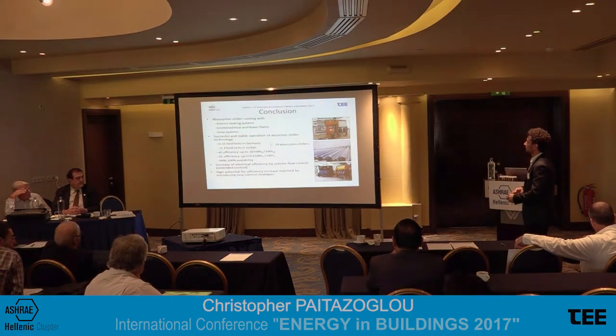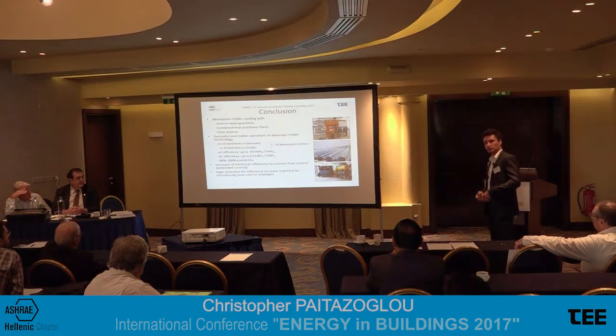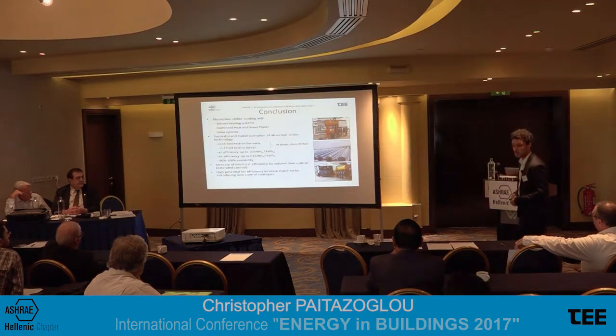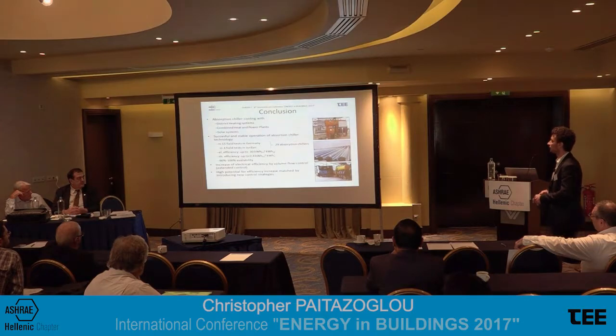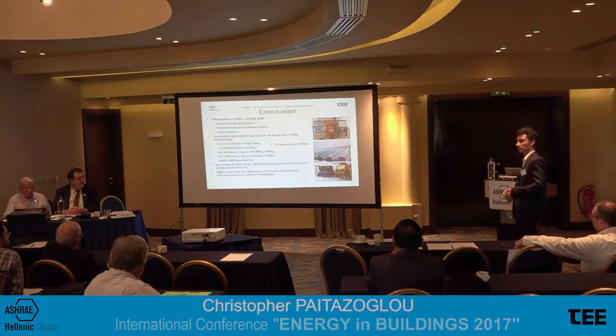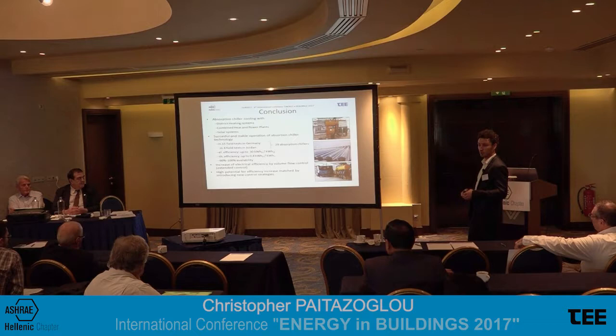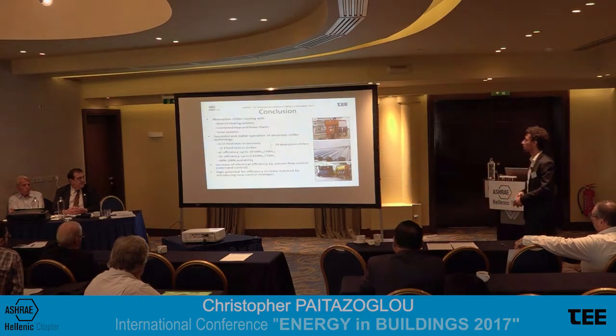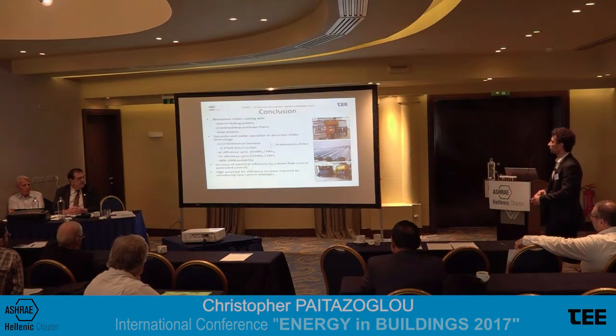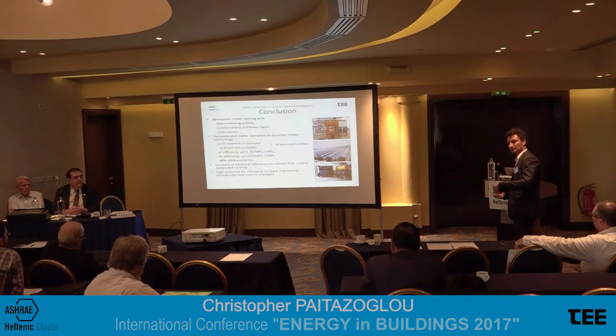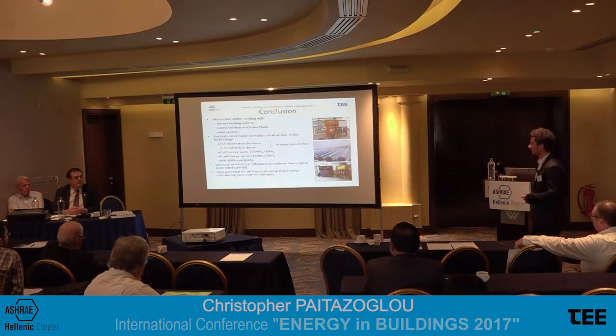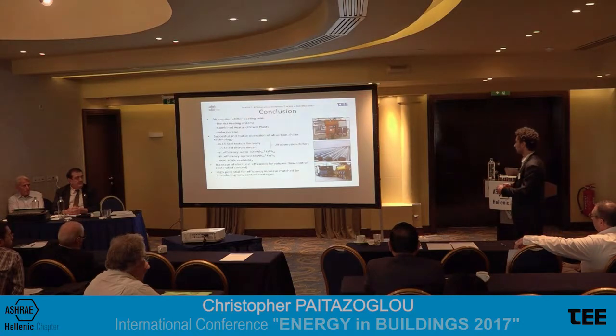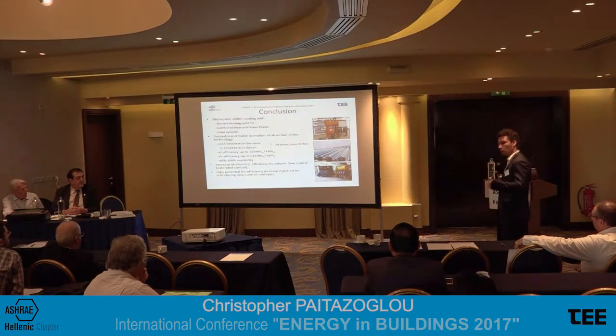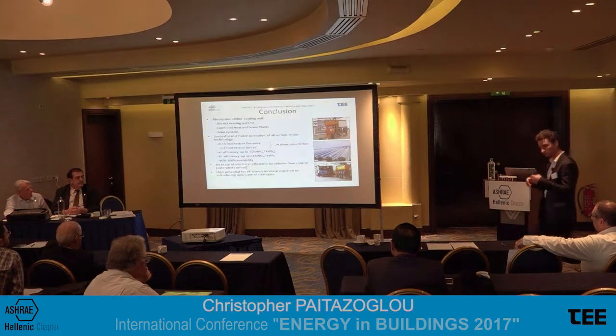In total, we are dealing with 29 absorption chillers, 15 in Germany, 4 in Jordan. The electrical efficiency of those systems is reaching values of 30. This is quite a number. The thermal efficiency can reach values of up to 0.8. That is the nominal point as promised in the data sheet. And this is very important for those companies or buildings that need the security that they will get cooling out of this chiller, which means there's almost 100% availability, not to say 100%.